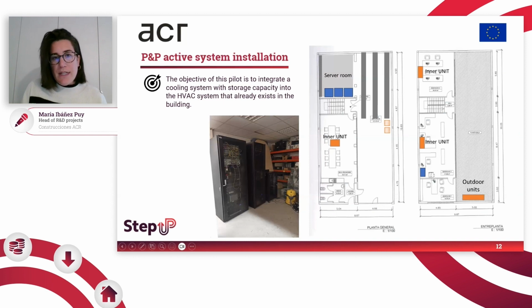The objective of the second pilot is to integrate a cooling system with storage capacity into the HVAC system that already exists in the building, without direct connection to the refrigerant liquid. That means the connection in the installation is made through air. The idea here is to demonstrate that we can cool the server room, optimizing electrical consumption.